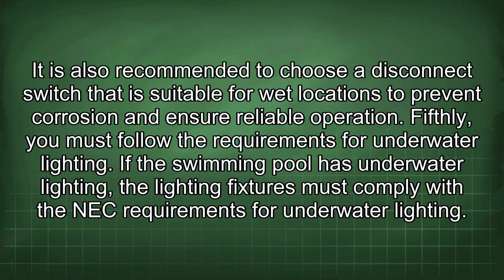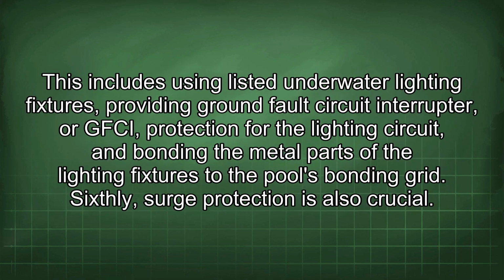Fifthly, you must follow the requirements for underwater lighting. If the swimming pool has underwater lighting, the lighting fixtures must comply with the NEC requirements for underwater lighting. This includes using listed underwater lighting fixtures, providing ground fault circuit interrupter, or GFCI, protection for the lighting circuit, and bonding the metal parts of the lighting fixtures to the pool's bonding grid.